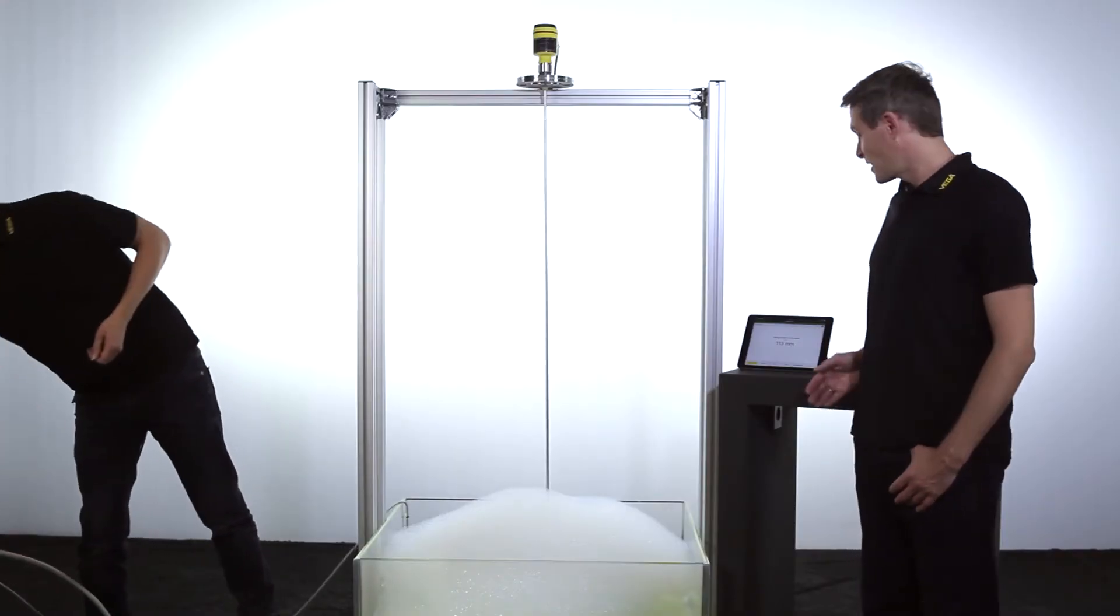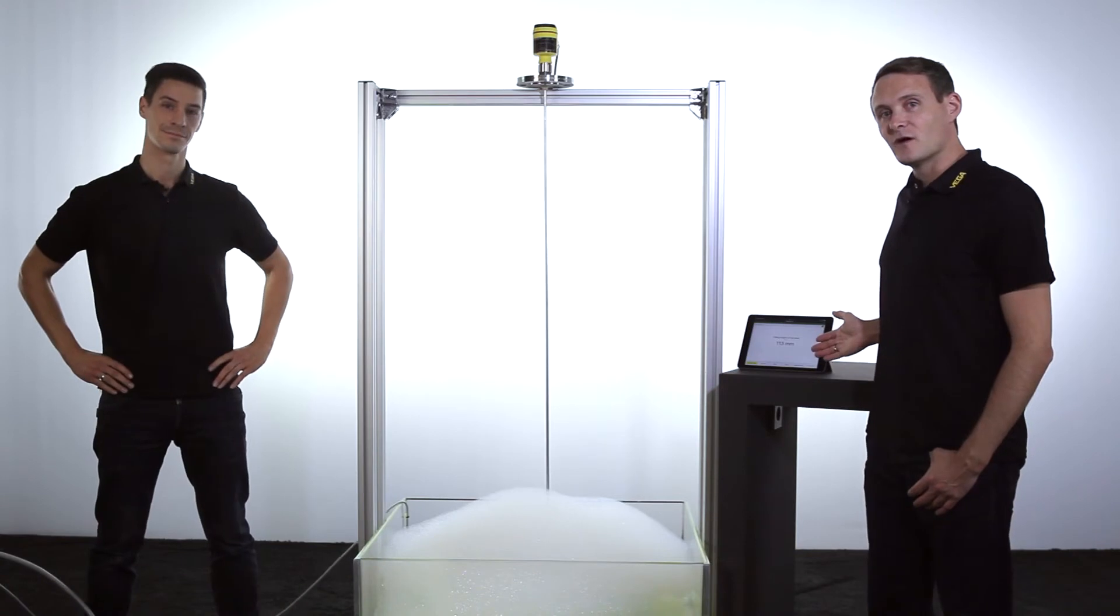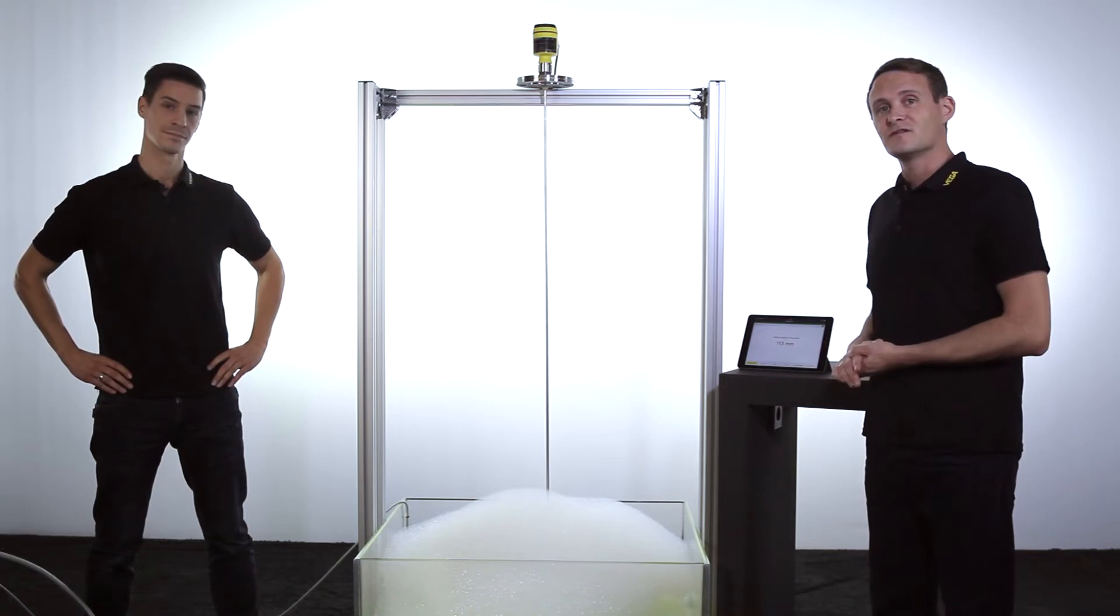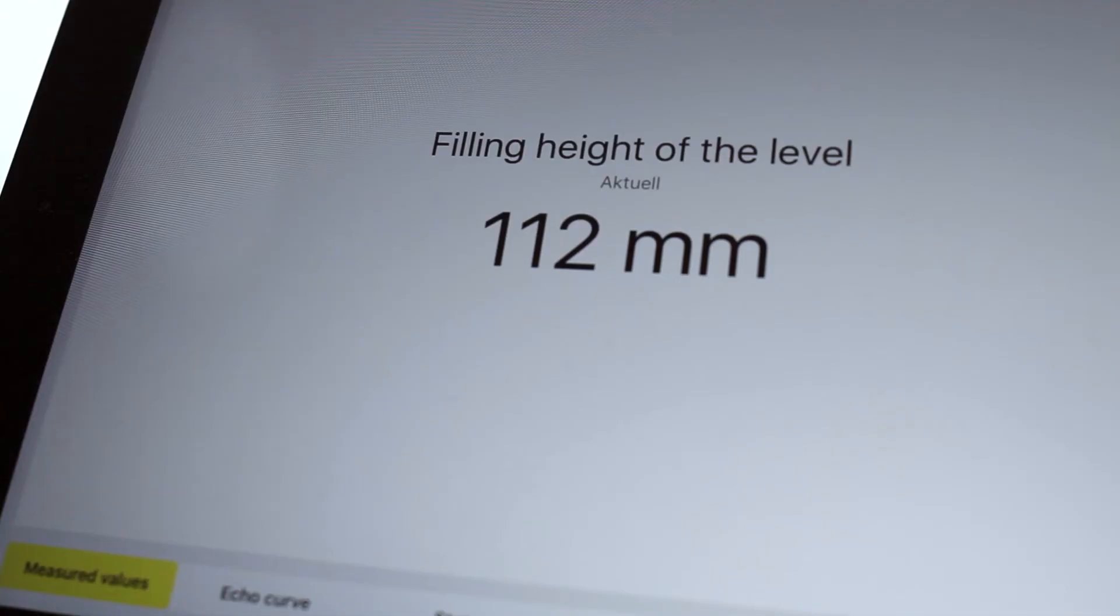You can see now on the display the measured value is only changing by a few millimeters, although we have a very thick layer of foam. So we measure really down through the foam to the level and the measurement is virtually unaffected by the foam.